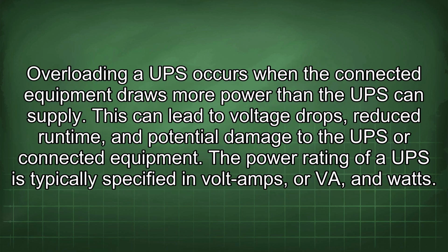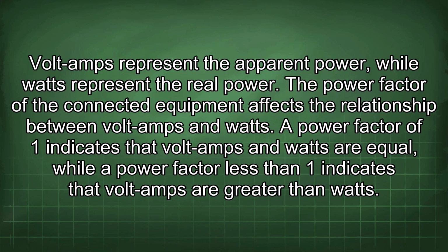Overloading a UPS occurs when the connected equipment draws more power than the UPS can supply. This can lead to voltage drops, reduced runtime, and potential damage to the UPS or connected equipment. The power rating of a UPS is typically specified in volt-amps, or VA, and watts. Volt-amps represent the apparent power, while watts represent the real power.